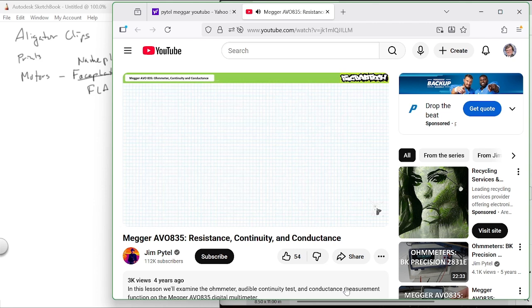In summary, if there's a connection, it beeps. If there's no connection, it doesn't beep. On a more sophisticated level, the AVO 835 emits a constant tone if the connection is below 5 ohms, an intermittent tone for connections between 5 and 50 ohms, and no tone for connections above 50 ohms.